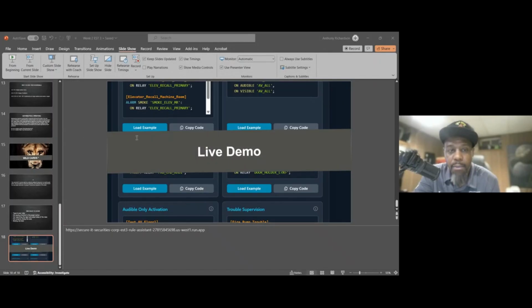So switch number 5, they want to turn on this control relay for the hatch and blink that same LED, flash it fast. And here they're using a global disable switch. So if they're doing any testing, any welding, any construction, whatever, they hit this switch, the last switch, number 12, and number 12 is going to turn off everything. It's going to disable all of the output devices so that they do not go into alarm. And another thing I don't see here is usually they would put a priority, so that nothing else can override this unless you press the switch to turn everything back to normal.